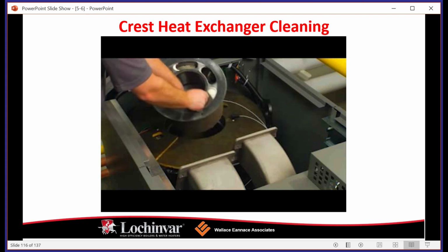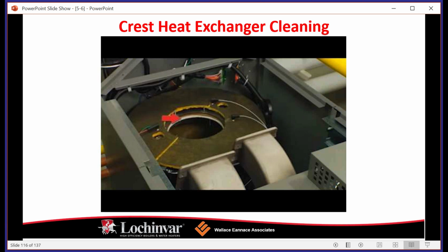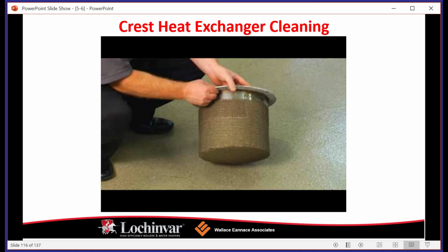Okay, if you do need to remove and clean a burner, you're going to use compressed air. You're going to use the gentle compressed air. Remember, we have that fiber mesh. You're going to inspect that fiber mesh. The fiber mesh should always be tight to the cylinder. If you hold it horizontally, you shouldn't see any sagging. There shouldn't be any gaps.